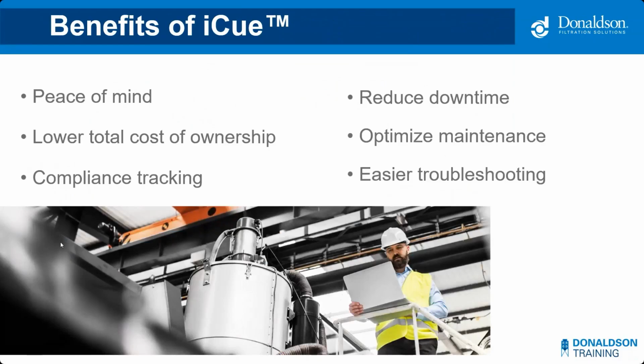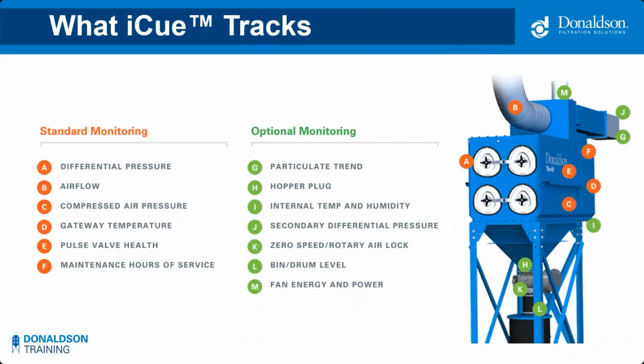It's not always obvious when there's an issue with the dust collection system until there's a major issue. And now production has to shut down in order for the maintenance team to come in and fix it. It can also be a challenge to identify the root cause of an issue. So having the data at their fingertips is very useful when it comes to troubleshooting, and also helps with compliance record keeping. So here's what our remote monitoring system can track. Again, most companies are starting to offer this. There's things like differential pressure, airflow, if an operator forgot to turn on the compressed air, if the bin level is getting too full, etc. Again, most manufacturers are offering this, and customers really appreciate it, and it's something to consider when specifying a dust collection system.